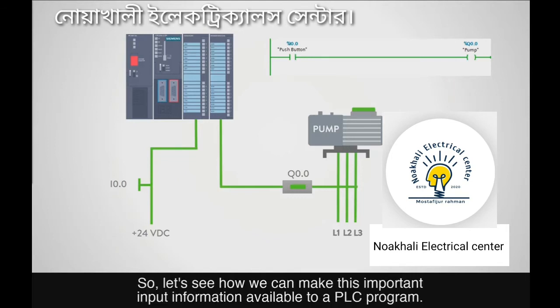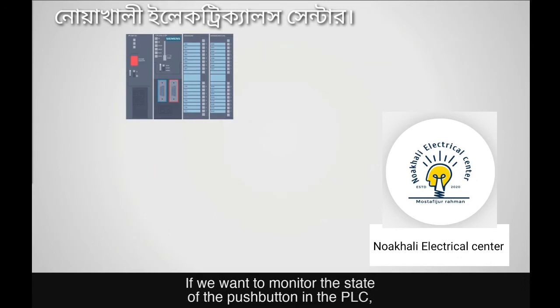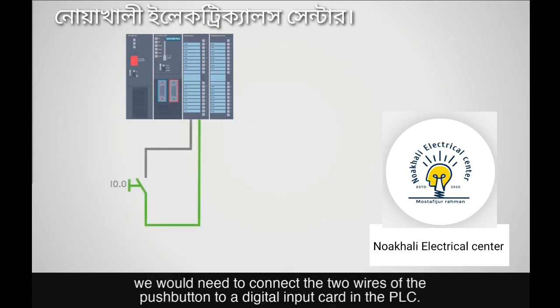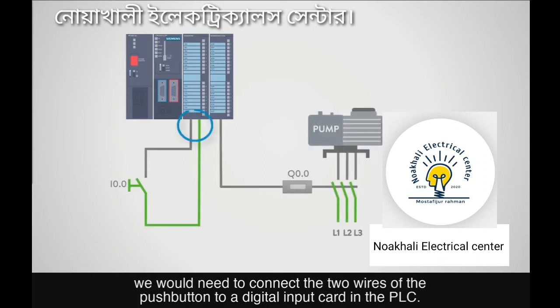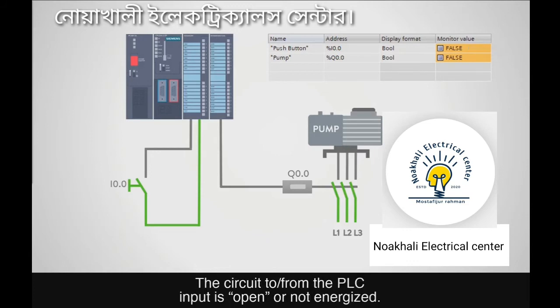Let's see how we can make this important input information available to a PLC program. If we want to monitor the state of the pushbutton in the PLC, we would need to connect the two wires of the pushbutton to a digital input card in the PLC. When the pushbutton is not pressed, the PLC would see the input state as OFF or as a 0. The circuit to or from the PLC input is open or not energized.